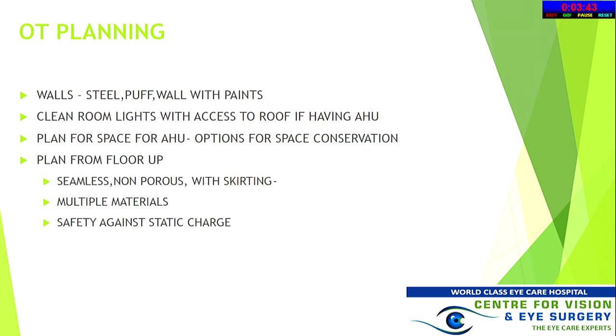Clean room lights with access to roof is important. You can have roof-hung air handling units also, these are now fairly common. Some people prefer an external unit, which will then need to be kept on the roof, so you need to provide space for that. If your operation theater is on the first floor and you have a terrace on the second floor, that is ideal, because the distance that the vents have to travel is very less. You can have interconnecting vents. Kumran will touch upon more, but there are slight variations in different types of air handling units as well.